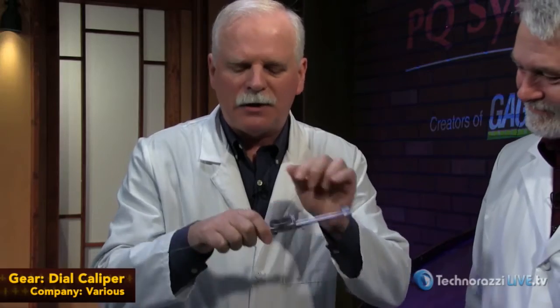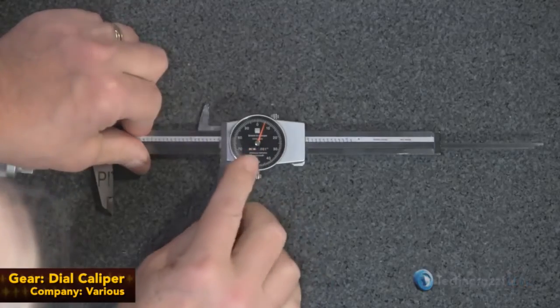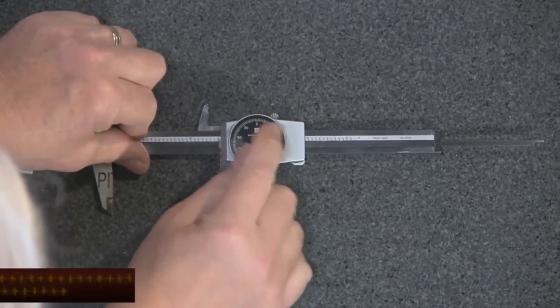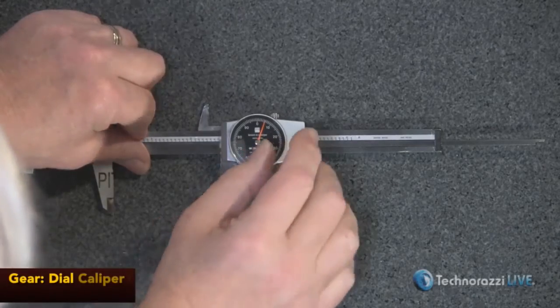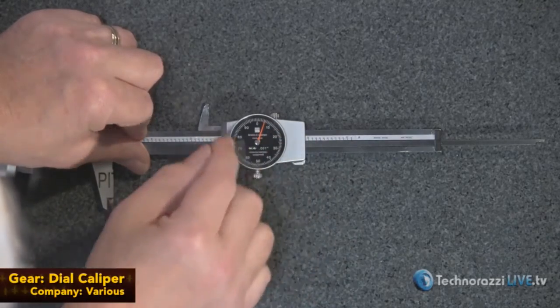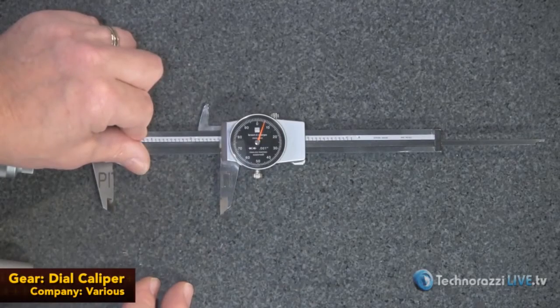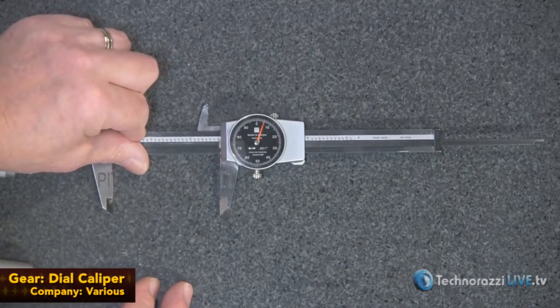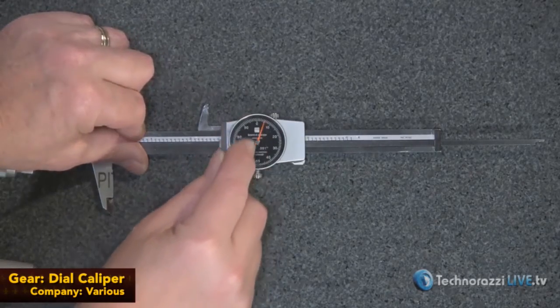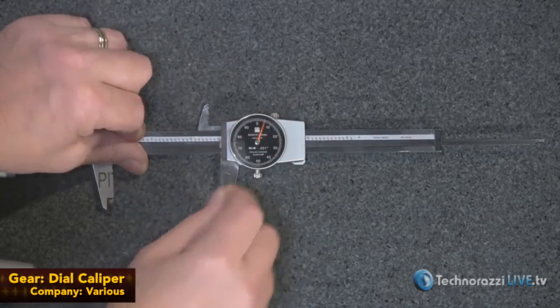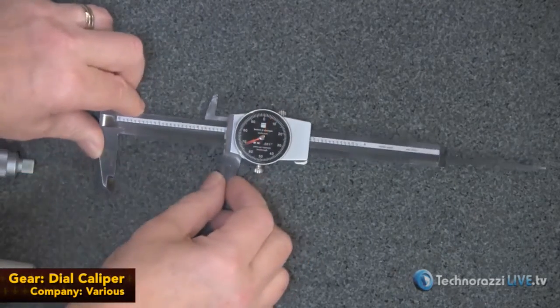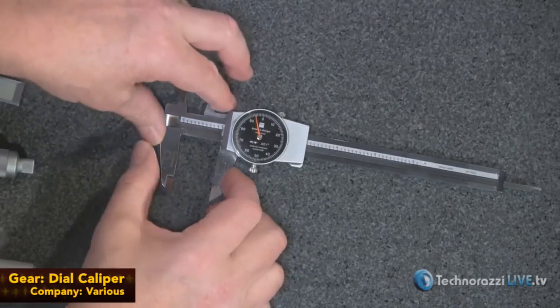Look very carefully inside. Let's go to the gauge cam. On the actual dial, there's a crystal, which is the glass piece above it, and then the dial below. Look for lines and wear which might indicate rubbing, that the hand has been rubbing one of the two. The hand itself, make sure it's straight. We've seen some that had some very artistic curly cues in them. I can imagine how that might have happened.